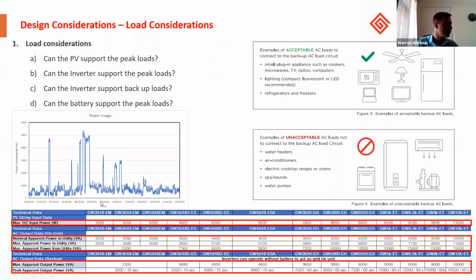So we look at products offered by GoodWe, and the peak load in this case is just over 5 kilowatts. We'll look at the nominal apparent power to the utility grid, and we've got a possible solution here with the GoodWe 5 kilowatt EM. The GoodWe 5 kilowatt ES can do a majority of that load, and both the GoodWe 5000 EH and the 6000 EH can deal with that peak load in terms of PV.